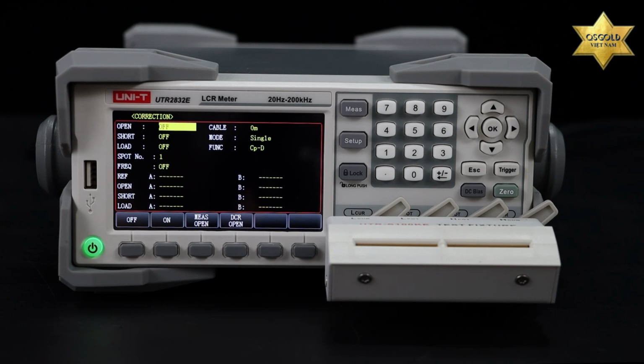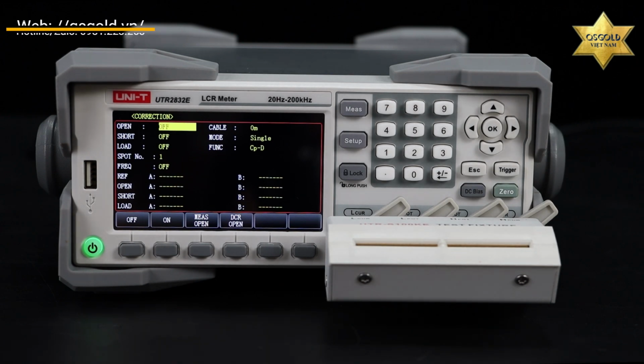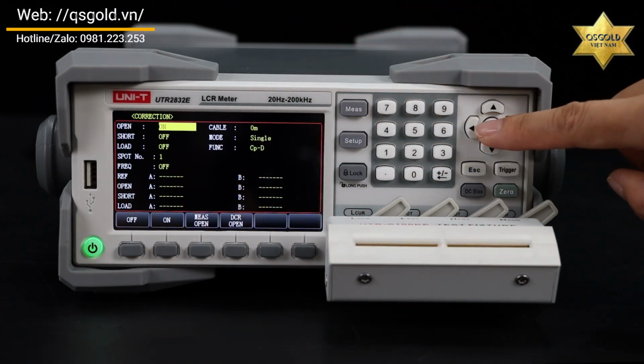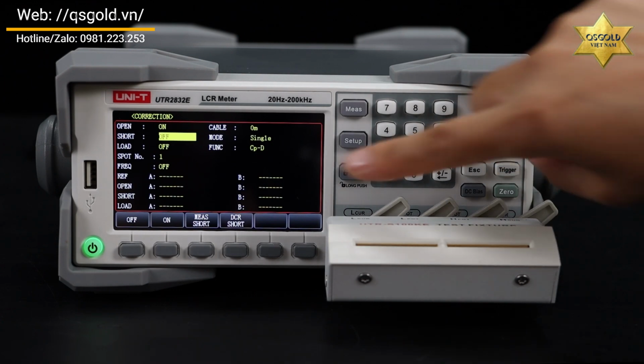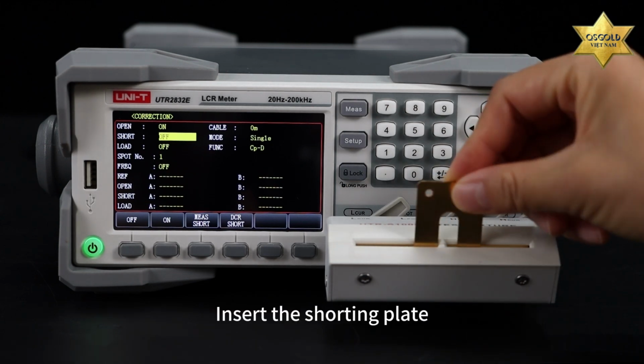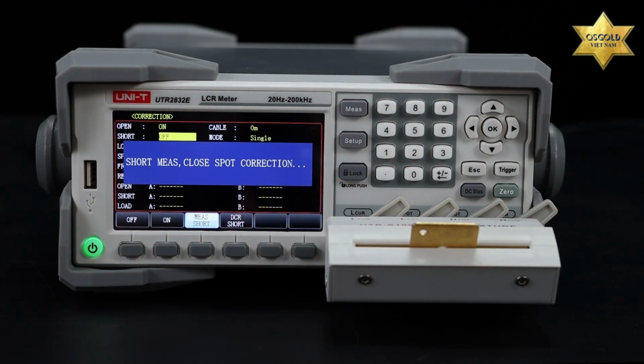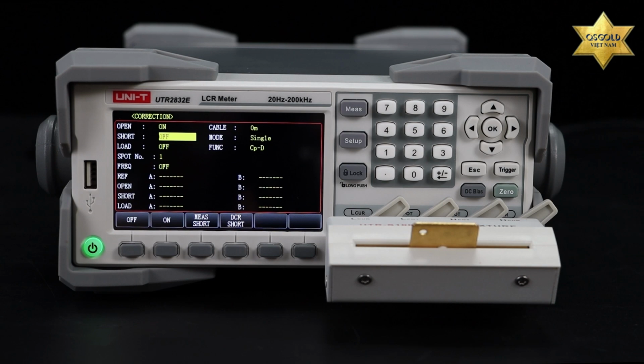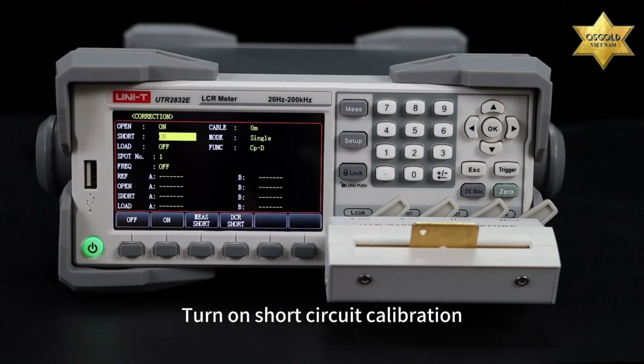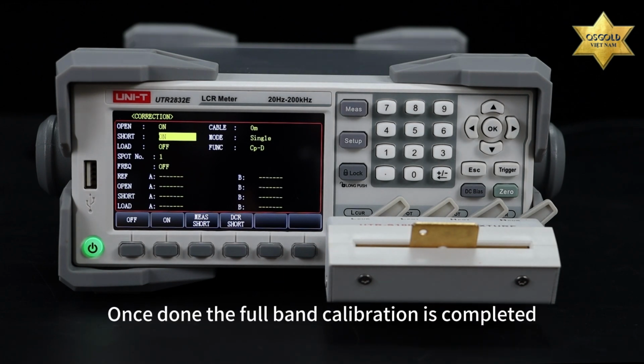When calibration is complete, we'll turn on the open calibration. Select Short Circuit. Insert the shorting plate. Turn on short circuit zeroing. When calibration is complete, turn on short circuit calibration. Once done, the full band calibration is completed.